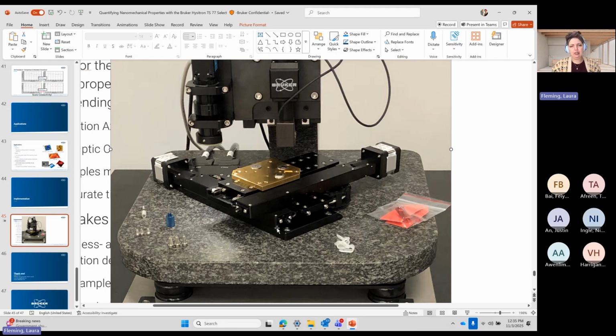Take that tip tool, come up, and as you're installing, don't hold on to the transducer. Let it move away from you as you're installing. The second tip is to go backwards first. That makes sure that the threads of the probe and the threads of the transducer are aligned. In really quiet labs, you can actually hear the click as those threads align, but mostly people feel it. It's really obvious. So backwards, feel the click, and then you move forwards.